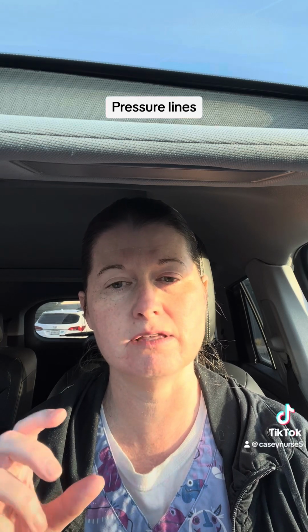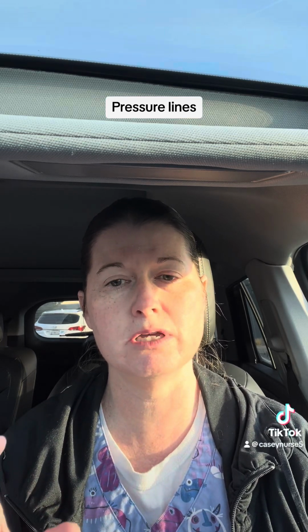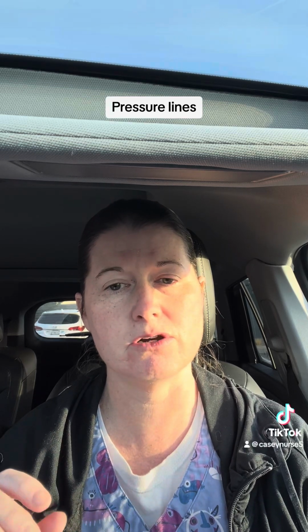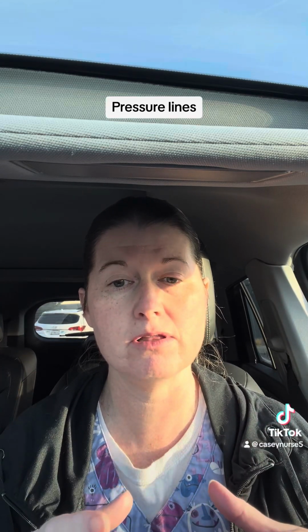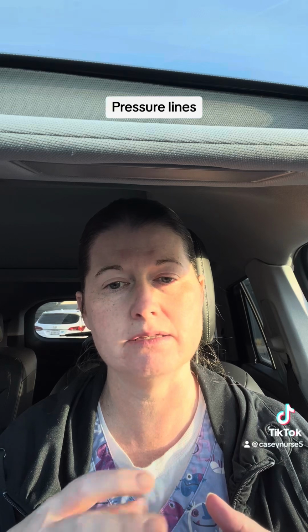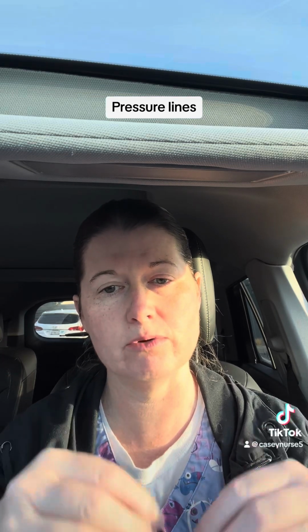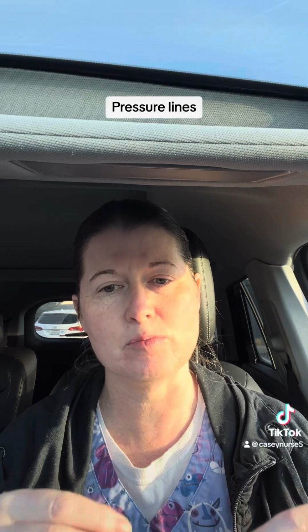Other things, you have to zero your line if you think there's anything wrong with it, when you're troubleshooting, when you're first hooking it up, and at the beginning of your shift. All of those times you want to zero it and make sure that the atmospheric pressure is kind of ignored. So just like when you put something on a scale and you have a tare weight where you make it 0 and you say this plate is 0, ignore the plate, only weigh what's on top of the plate. Same thing with the pressure tubing.